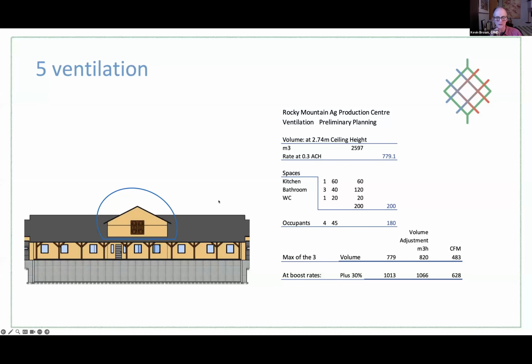Is like this. I'm just going to share my screen back to that slide because it was more important than perhaps I should have given the time for, right? So in the Passive House system, there's a three-part situation. What you do is you calculate the entire volume of the space. So at the top part of the chart there, volume at 2.74 meter ceiling height, so there's the volume in cubic meters. And what you want to see is the air change rate of 0.3 air changes per hour.